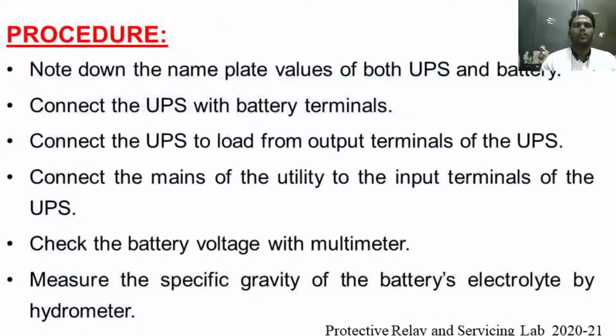So after this, the procedure for the installation of the UPS connected to the battery and to my load. Initially, note down the nameplate values of both the UPS and the battery. Next, connect the UPS to the battery terminals with my connecting wires. Connect the UPS to the load from the output terminals of the UPS. Next, connect the mains of the utility to the input terminals of the UPS.